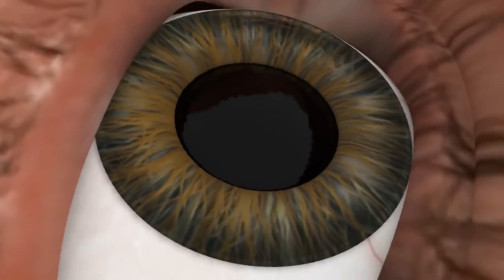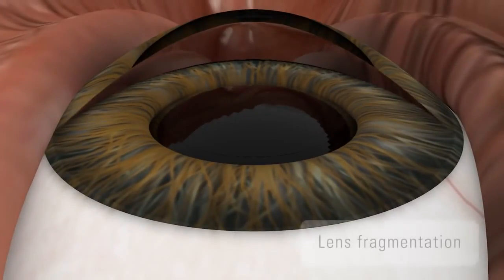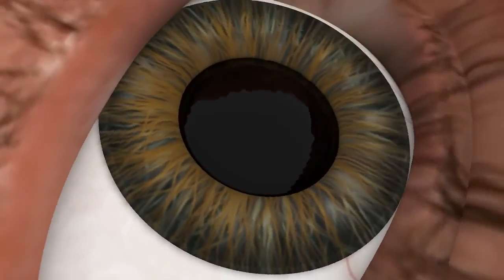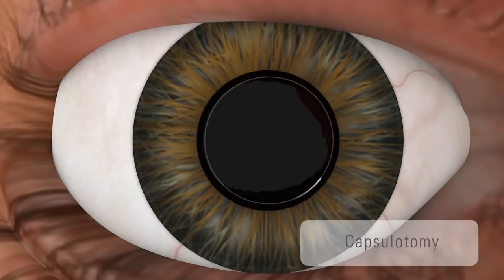All the planar sections for the femto cataract surgery are then performed. The lens can then be fragmented with different patterns. The laser pulse energy can always be adjusted, for example for different cataract grades, thanks to the adaptive pulse management system. In most cases, a perfect free-floating capsulotomy can be achieved without any tissue bridge, thanks to the overlapping spots of the laser beam.